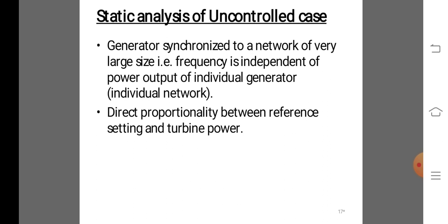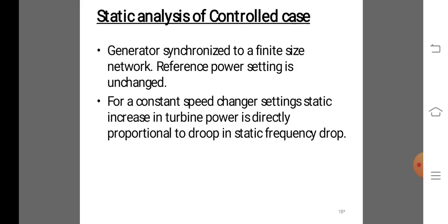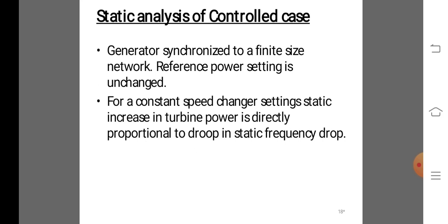There is direct proportionality between reference setting and turbine power. The second is static analysis of controlled case, where the generator is synchronized to a finite size network. Reference power setting is unchanged for constant speed governor settings. Static increases in turbine power are directly proportional to droop in static frequency.